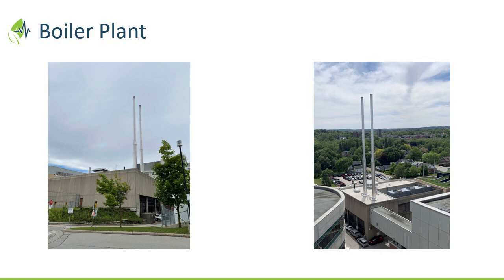And Paul, looking at that ABB on the right-hand picture there, is that a variable frequency drive? That's the variable frequency drive. And that's on the draft motor, right? That's on the combustion air, yes. And as you say, that's a big motor. And did you install that at the time, or was that already there? I think that was part of your upgrade, right? It was part of the upgrade. Yeah. Okay. And it depends, right? Like you can stage the stuff. These days, that's a very cost-effective measure to add at any time. So Vicky, there's big electricity savings there as well.